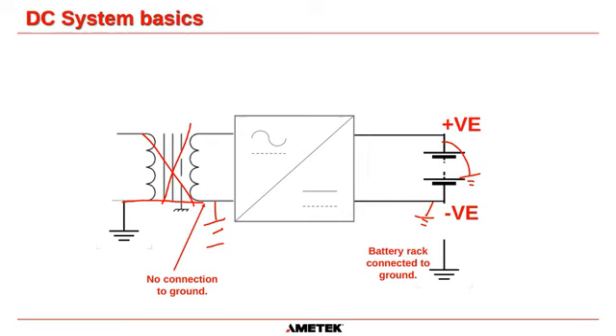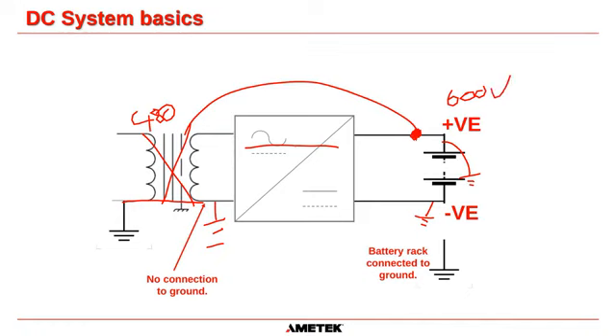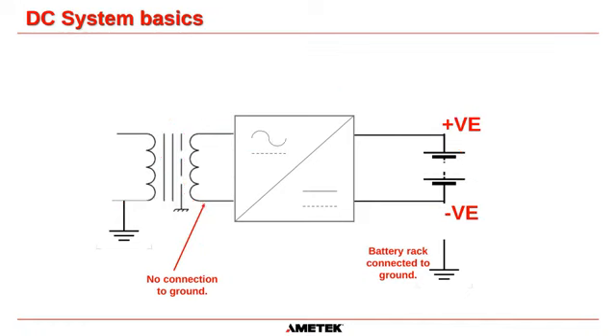And therefore, if an electrician does touch the positive post on a battery that doesn't have an isolation transformer in the charger, it's not a DC electric shock you're going to be getting. It's actually an AC electric shock that you'll be getting, because it's AC connected through the diodes and SCRs. And on a 480 volt system, the peak of that can be about 600 volts. So if you don't have an isolation transformer, you're putting your battery technicians in danger if the battery is not disconnected from the system when you're doing maintenance on it.